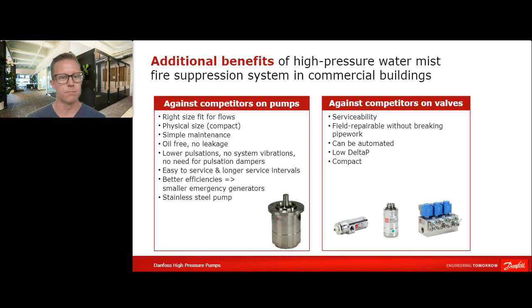So to sum it up, if we have a look on the pumps first, as mentioned, they're made out of stainless steel, making them highly reliable. The pump is very compact, making it easy to install also in tight spaces. And as mentioned, you can do that in both horizontal and vertical. The frame sizes that we have fit well to the applications and the flows needed. They are all lubricated by the media itself and only consist of few parts. So maintenance is very easy and fast to do.